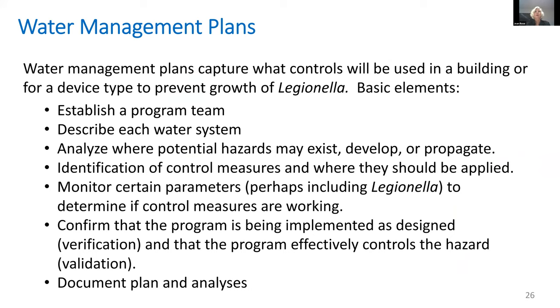One must establish a program team, which should be multidisciplinary. The water system should be described, and the hazards analyzed—where can Legionella grow and propagate, and where are the exposure sites? There should be identification of control measures and where they should be applied. Certain parameters, including in some cases Legionella itself, should be monitored, and there should be a determination of whether these control measures are working. There should be confirmation that the program has been implemented as designed and effectively controls the hazards.